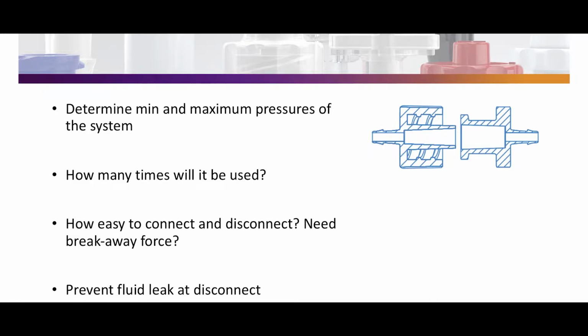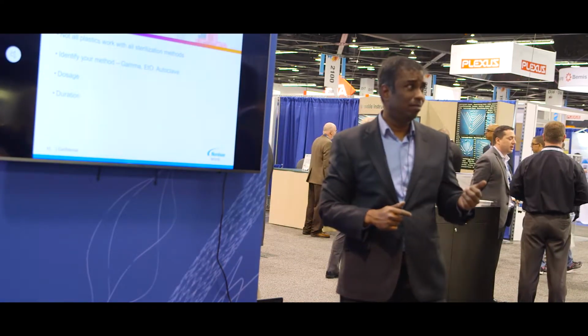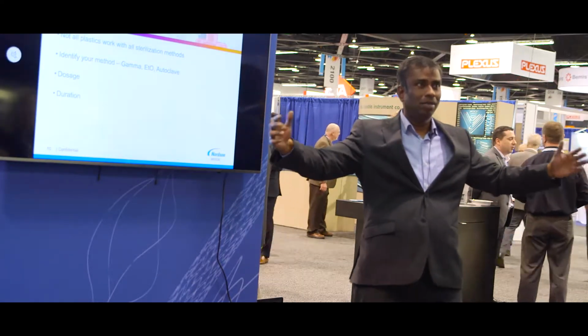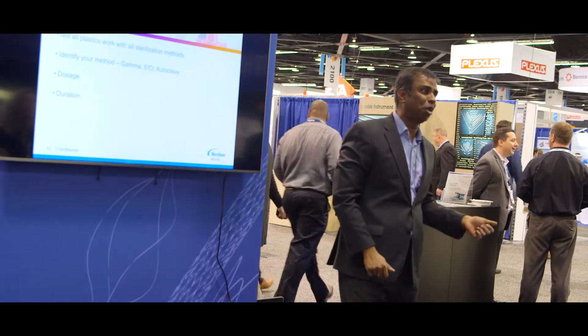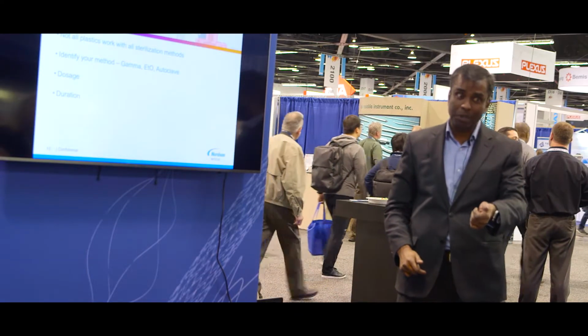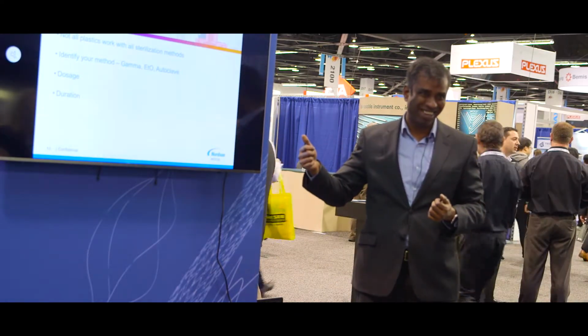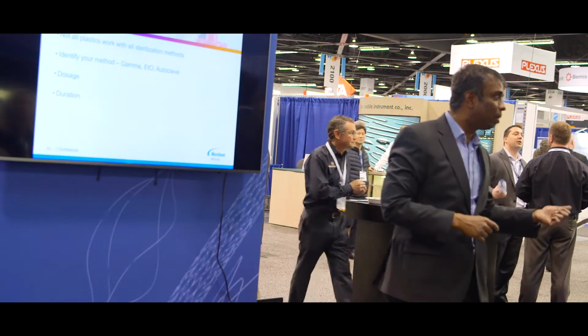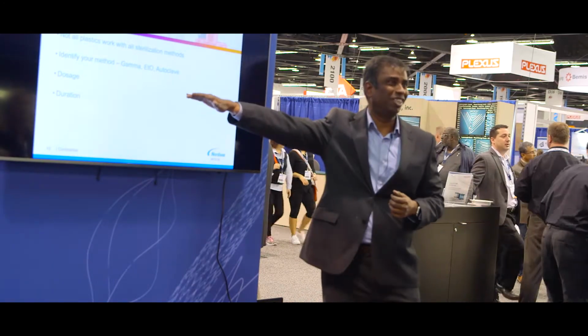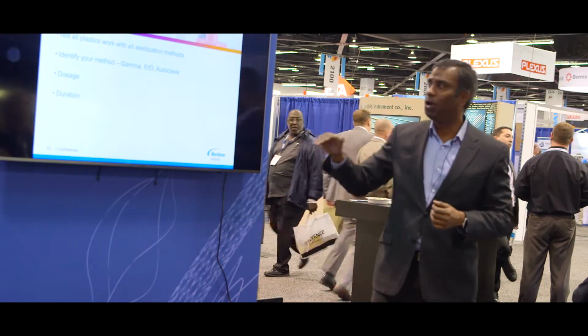What is your dosage, right? Most medical device products are gamma irradiated at 20 kilograys. But then you have this big pallet and some of the products are in the center of the pallet and don't get enough radiation if you're hitting it with 20 kilograys. So many people opt to hit it at 50 kilograys or 80 kilograys. So here's the thing: not all plastic materials are suited for sterilization. Acetal will only withstand like 20 kilograys, nylon 15 to 20, polypropylene 50, polycarbonate 50. You need to know what your dosage is. So in order to find the right fitting, you need to know your dosage, how you're going to sterilize, and what your duration is.